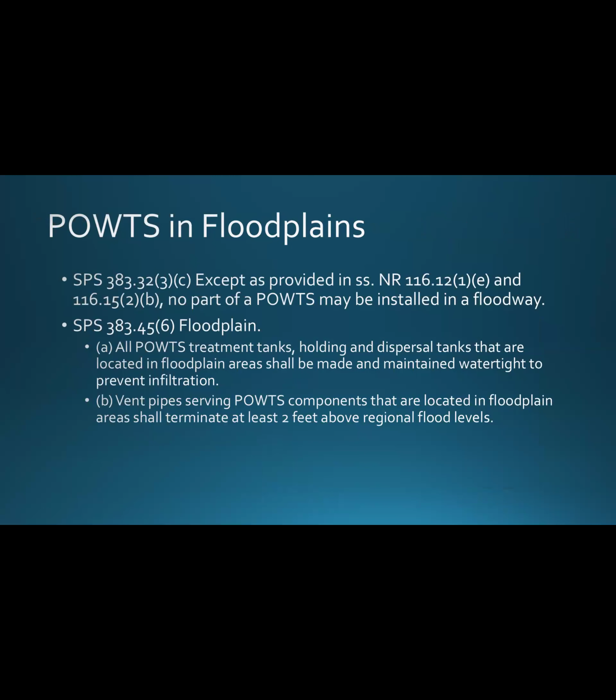So POWTS and the floodplains. What are the requirements for us? SPS 383.32(3)(c) says, except as provided in NR 116, and there's a couple sections here we'll look at in a minute, no part of a POWTS may be installed in a floodway. So we can't be in a floodway. And again, if we don't differentiate between those, then for instance, a zone A considers everything a floodway. We can't put any kind of system in there.